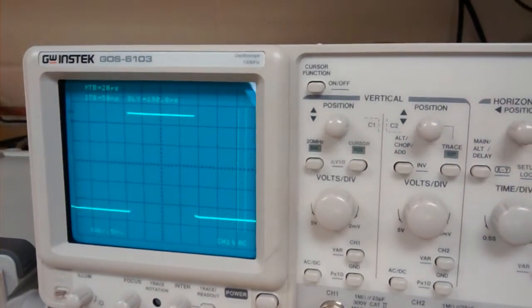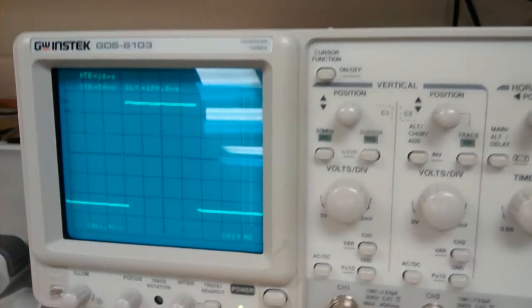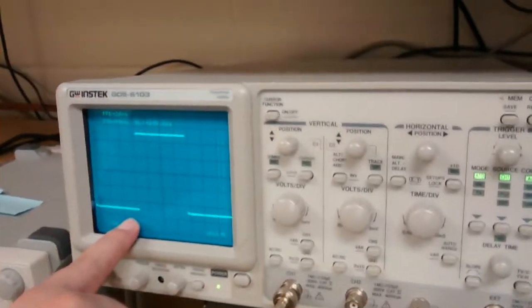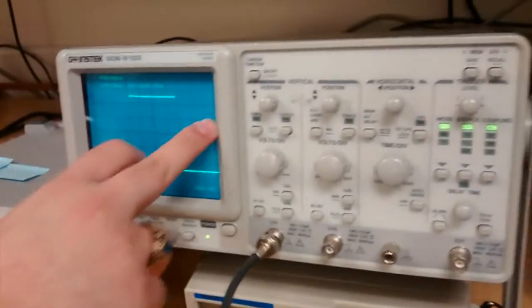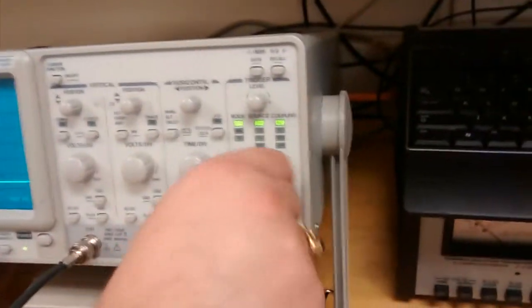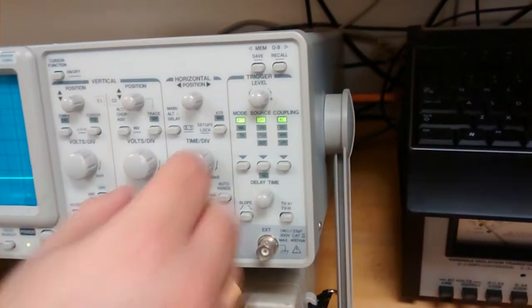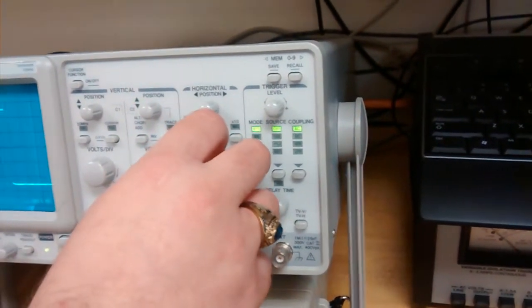And because you're trying to get, which is this one for, rise time? Yes. Negative to positive, so left side of the wave. If it's fall time, positive to negative, so right side of the wave. To move the bracket, you move the delay time knob. To expand or shrink the bracket, you move the time division knob.